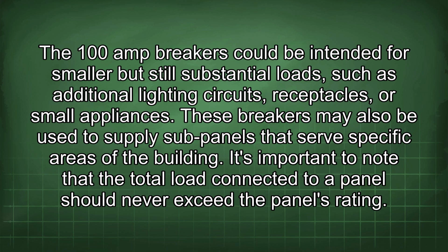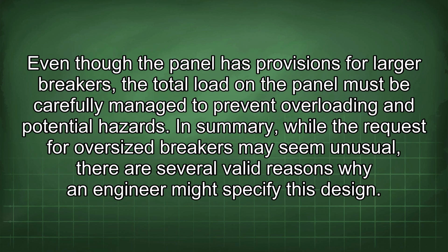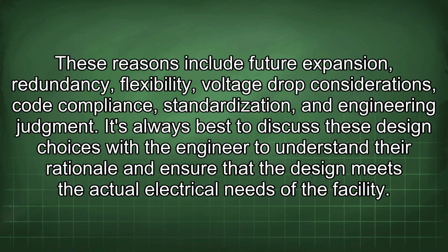It's important to note that the total load connected to a panel should never exceed the panel's rating. Even though the panel has provisions for larger breakers, the total load in the panel must be carefully managed to prevent overloading and potential hazards. In summary, while the request for oversized breakers may seem unusual, there are several valid reasons why an engineer might specify this design. These reasons include future expansion, redundancy, flexibility, voltage drop considerations, code compliance, standardization, and engineering judgment. It's always best to discuss these design choices with the engineer to understand their rationale and ensure that the design meets the actual electrical needs of the facility.